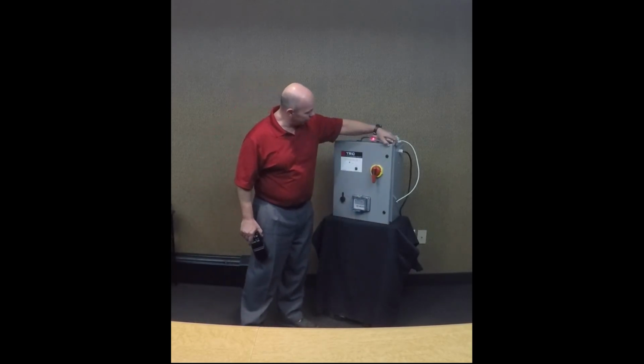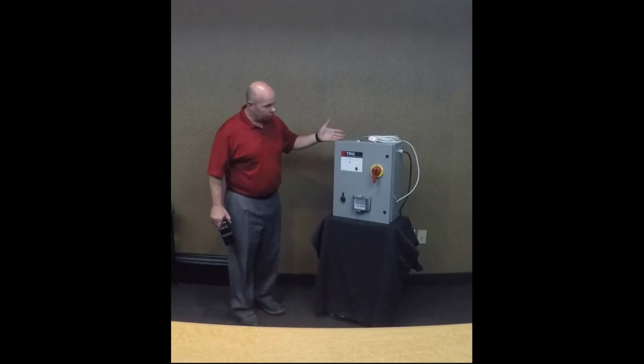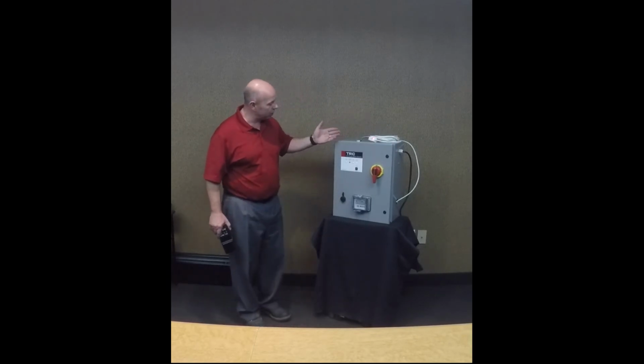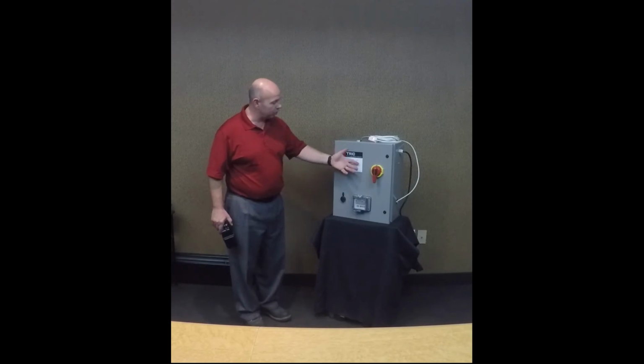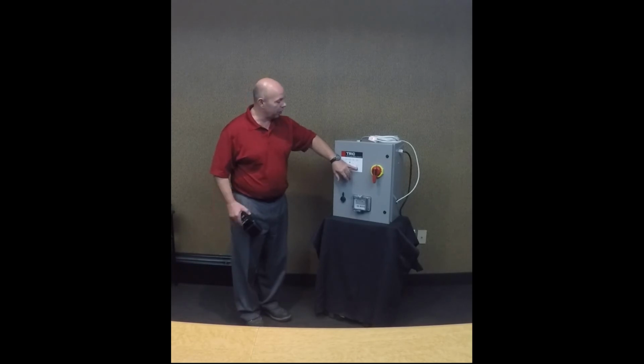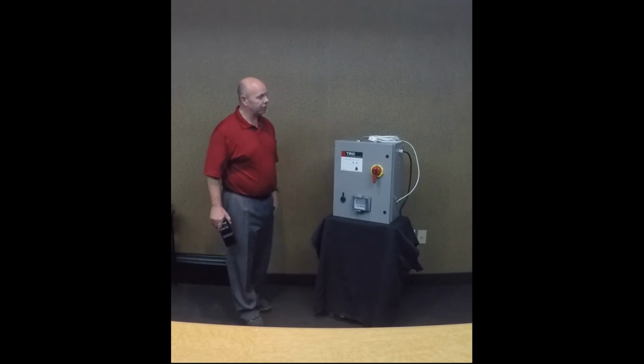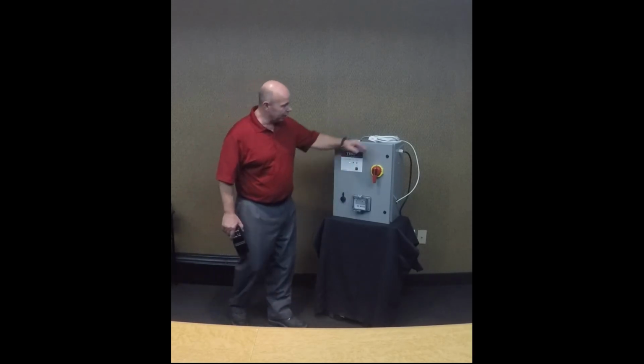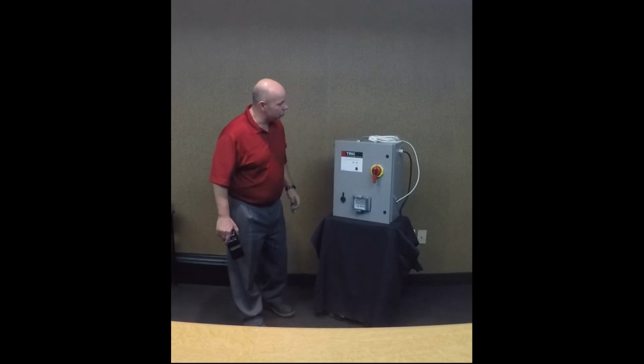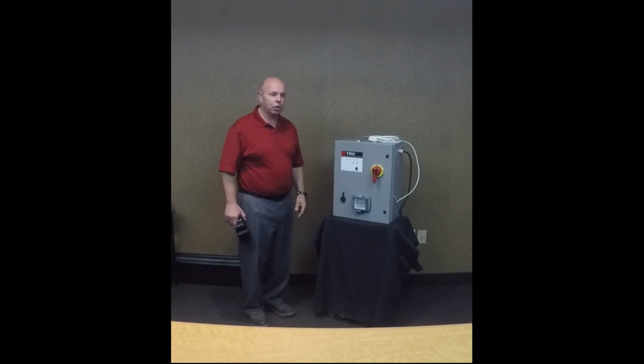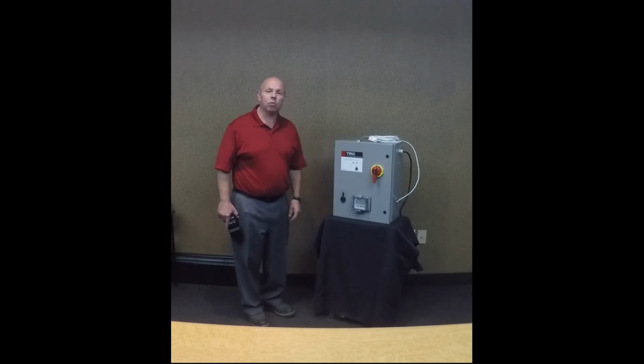You can see here from the front that the arc flash relay system has been tripped. We have power on, but we have system tripped. And so to reset this at the end of determining what caused the arc flash event, it's just simply by resetting the button, and the system is back online. Again, a very easy system to use in those locations where you have existing switchboard, switchgear, motor control centers, industrial control cabinet, as well as industrial machine. The TRC P1 arc flash relay.